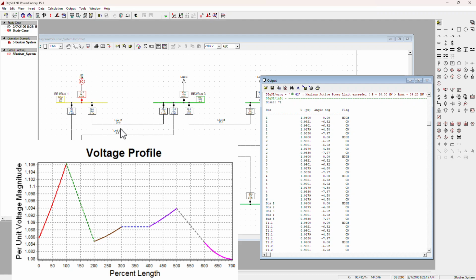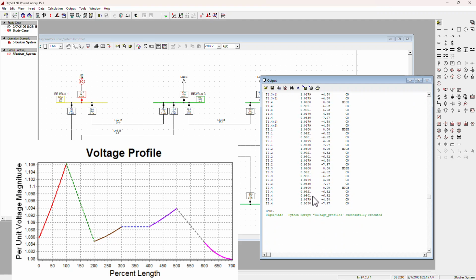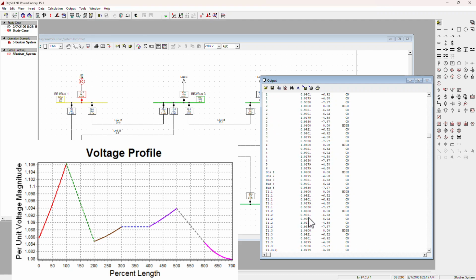Depending on which one is acting as a slack bus on this network, that slack bus is regulating for a particular per unit voltage at a bus bar. So it will be pumping reactive power to make sure it can maintain the voltage profile at that same level, to ensure that the voltage does not dip or go too high, depending on what's going on here.